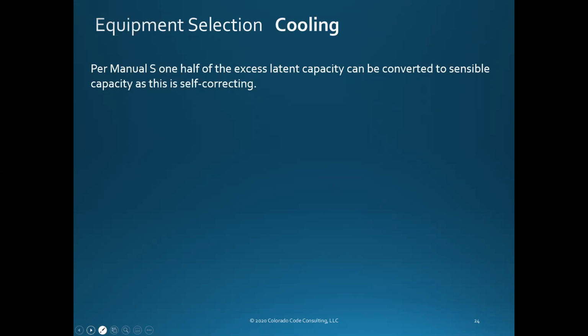We're taking this nice warm moist air and passing it by a cold coil inside the furnace. The more air I'm moving through there, the warmer that coil gets. Do you agree? So I'm moving more air, getting that coil warmer, and what's happening less? Well, the colder the coil, the more water will condense on it. It's physics, the warmer the coil, the less condensation we get because it's warmer.